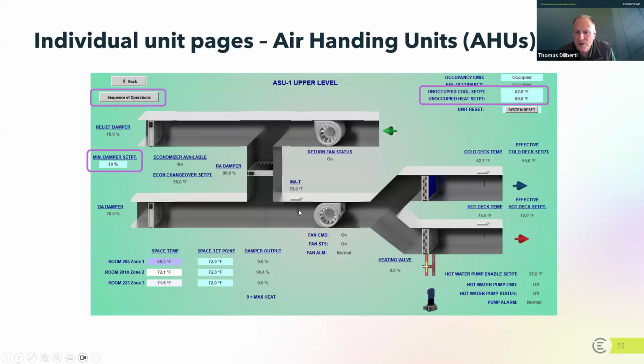And then talking through the system here a little bit. This is an air handling unit. So what's happening here is the air is coming in from this outside damper. So it's set at 10%. So air is coming in this situation. It's going across the fan. It's being split into a hot deck and a cold deck. It's going to be recycled. So the air that's returning here, it could be ejected from the building, just exhausted out of the building, or it could be recycled. So the air flow through the system. But I wanted to highlight this idea of the minimum damper set point.